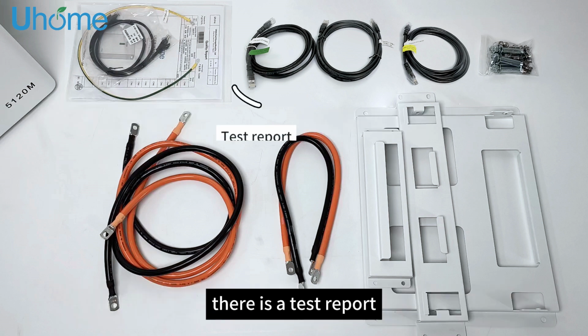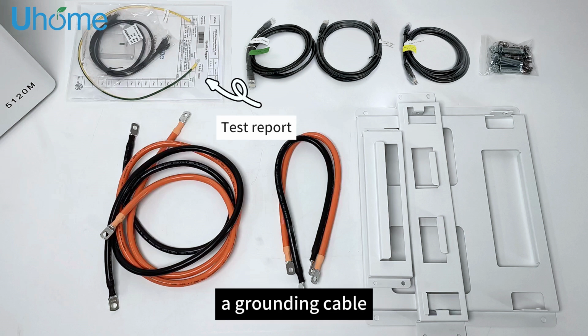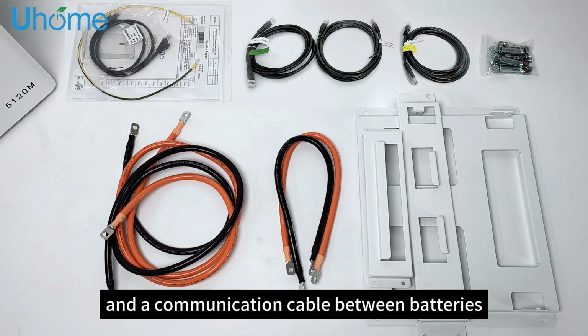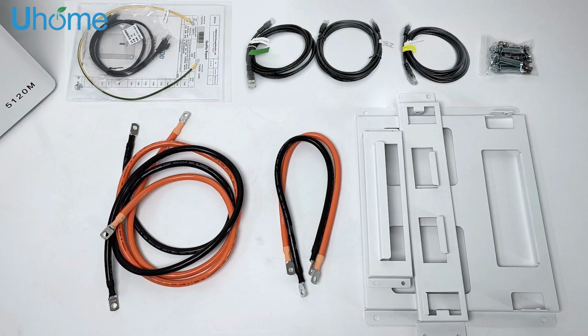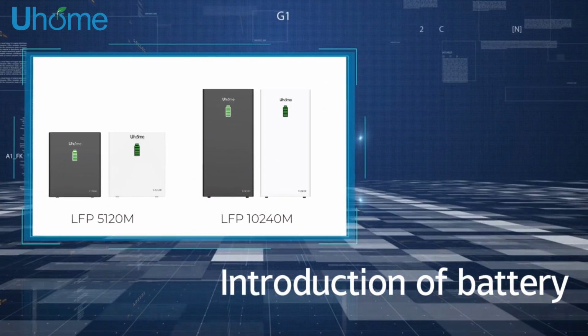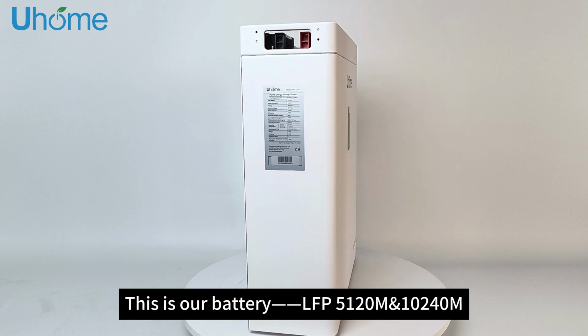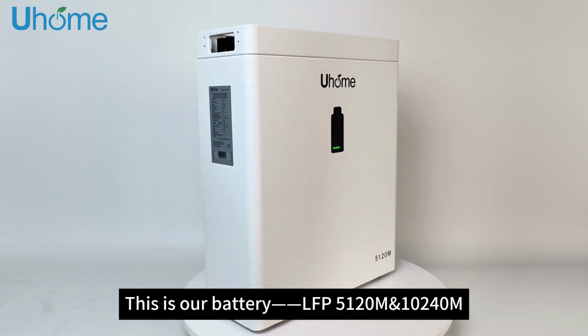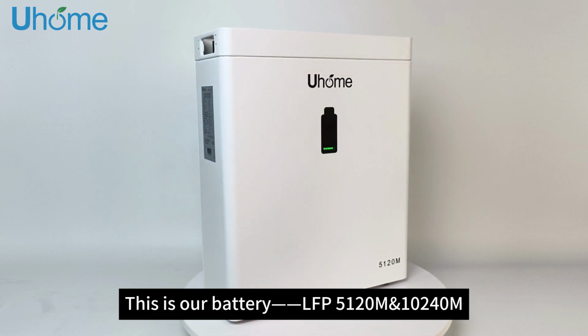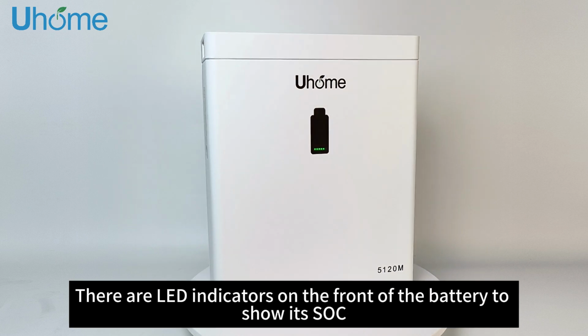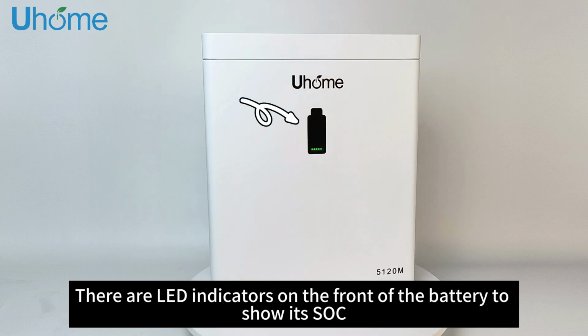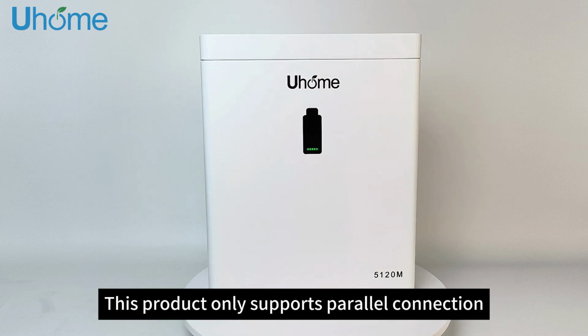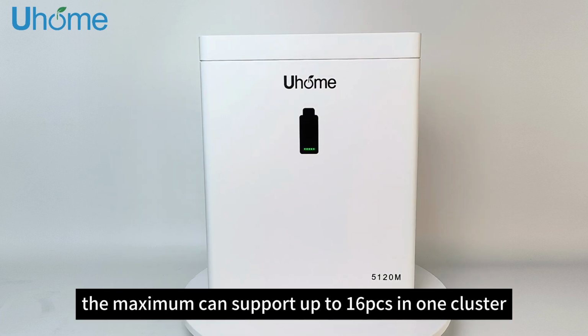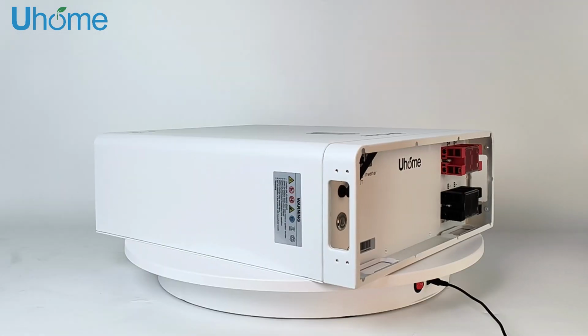There is a test report, a user manual, a grounding cable, and a communication cable between batteries. Introduction of battery. This is our battery, LFP 5120M and 10240M. There are LED indicators on the front of the battery to show its SOC. This product only supports parallel connection. The maximum can support up to 16 PCS in one cluster.